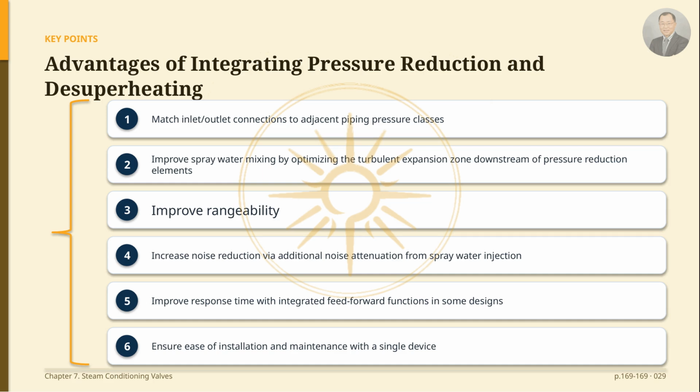Now, I would like to introduce the advantages of integrating the pressure reduction and desuperheating functions into a single valve rather than using 2 separate devices. First, the inlet and outlet connections can be more closely matched to the adjacent piping. Also, spray water mixing is improved because the turbulent expansion zone formed downstream of the pressure reduction elements is utilized optimally.